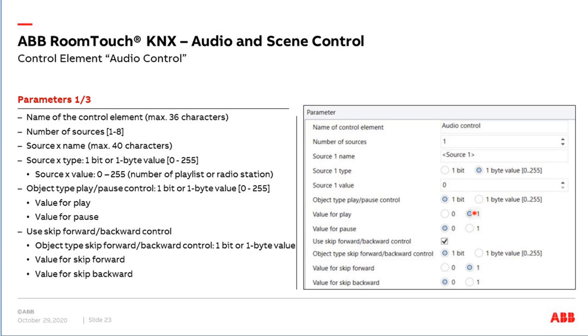Now let's look at the parameters of this audio control element. The first parameter is the name of the control element — for example 'Music' or the name of the room — which is displayed in the RoomTouch for the end user. The number of sources is maximum eight, meaning we can call up to eight different playlists or radio stations. For each source we enter the name, the type (one bit or one byte — recommended is one byte), and the value. If the value is one, we call the first favorite; if the value is five, we call the fifth favorite in our playlist.